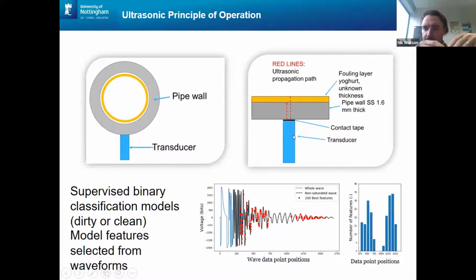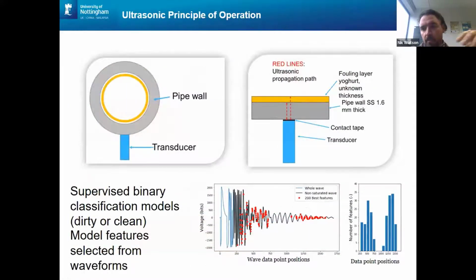So on a lab scale, we have a nice little open top, and we have a flat piece of stainless steel. We can put our fouling on it. We can flow through cleaning fluids and chemicals. We've got a camera on top, so as we're recording our ultrasound, we can see from the camera whether it is dirty or clean. Then we can label our ultrasonic signals as either dirty, when there was fouling there, or clean, and then develop our supervised machine learning models. So this is binary classification: is there fouling there, yes or no?